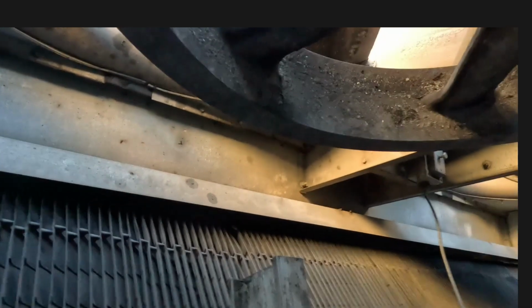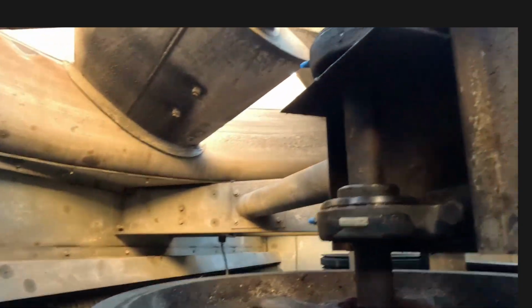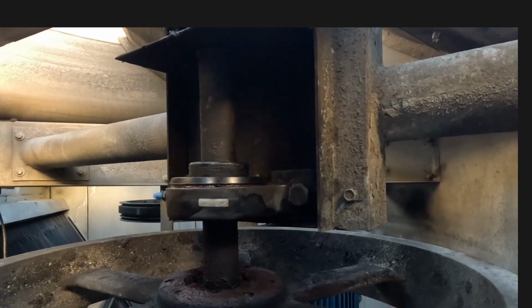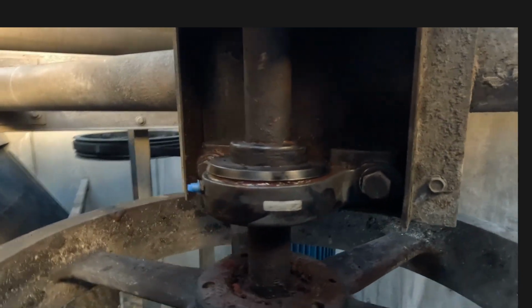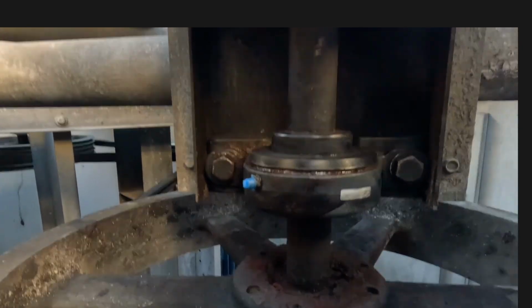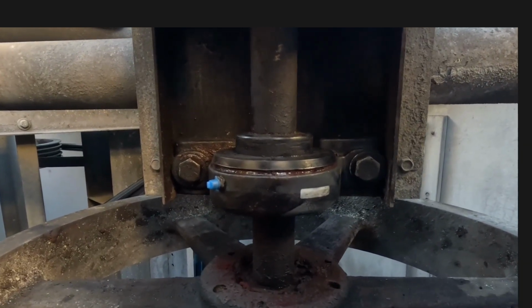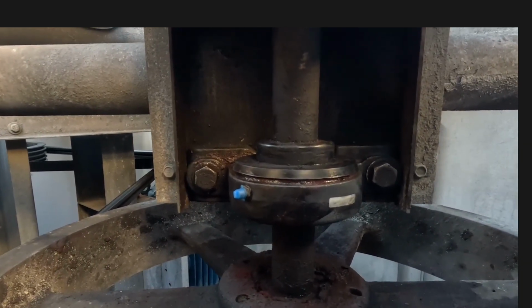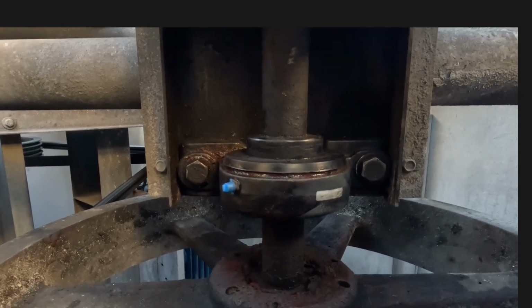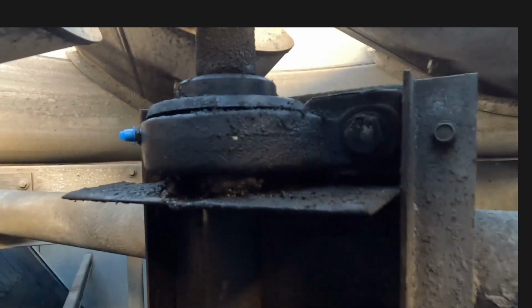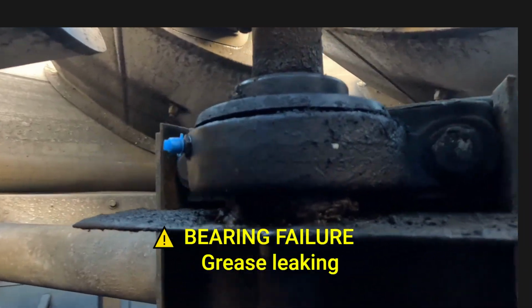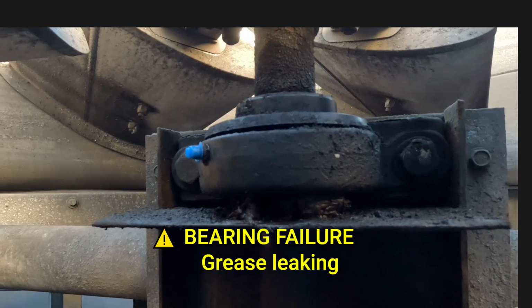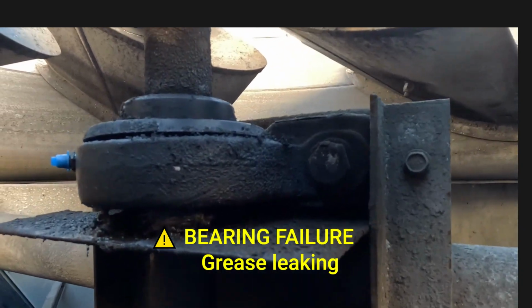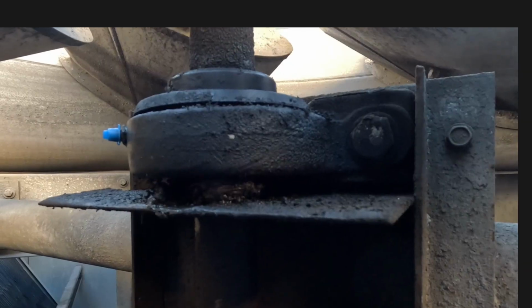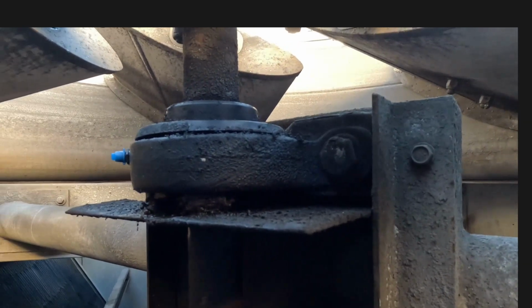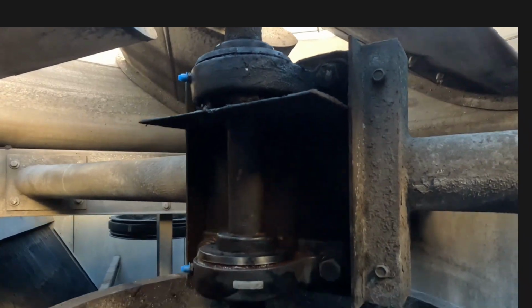I got to recommend to the customer that he's got to replace the bearings on his cooling tower here. It looks like the bearings, I cleaned them up already, and I added this little blue Zerk fitting cover just so dust and crap doesn't get inside my bearings there. So there's where you place the grease gun, and then just start pumping grease in there. Like I said, it looks like they greased the bearings prior to me getting this account, and they blew out the bearings, right? You're not supposed to have grease all over the place like that. That's a sign that the packing inside that bearing has failed, and all the grease is just starting to spill out. In any case, this is what I'm recommending for the customer to do.